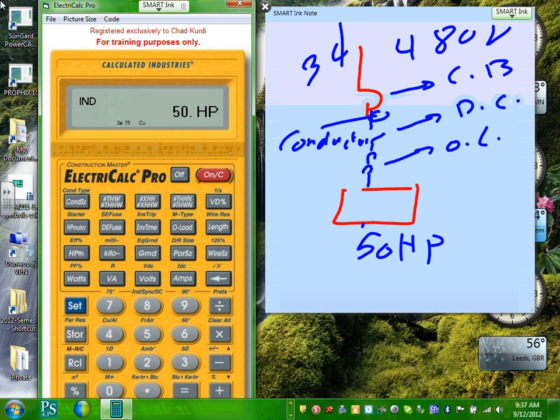Everybody put that in? Now, let's see what the full load amp is for this motor from the NEC code book. Now, just the full load amp. Okay, can you guys hit amp here? This is 65 amps. If you go to table 430.250, it will tell you 65. Now, it gets easier. Hit the amps again. Oops, it doesn't take you to the table, does it take you guys to the table? Okay, so 65, this is coming from the code.